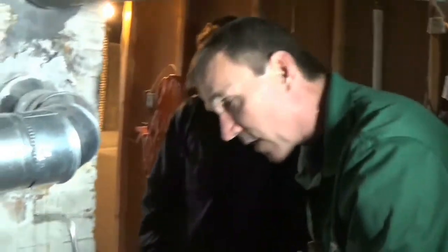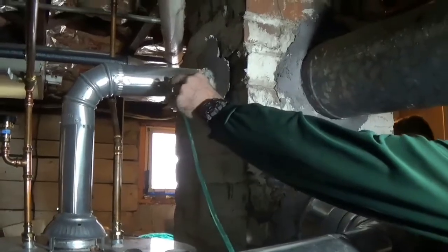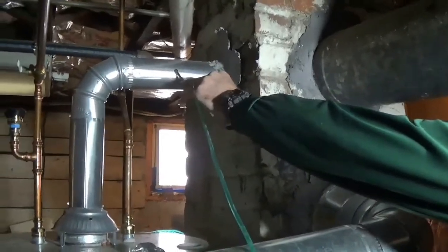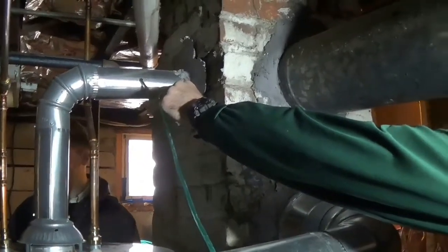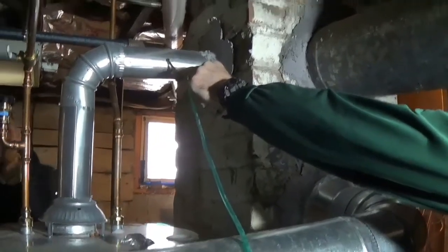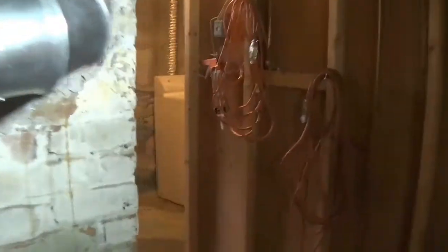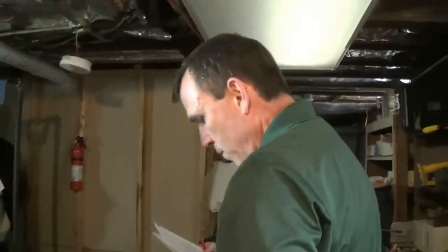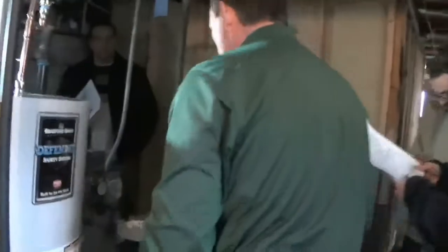So I wait for this to settle down. I put it right into this hole. I look at my number, and I've got like a minus 1 point. So it's looking good. The draft is looking good. The draft is looking like minus 2.2. All right, so I'm going to write that down. Now I'm going to turn my boiler on. Minus 2.2, I write down for the draft for the domestic hot water without the heating system going.